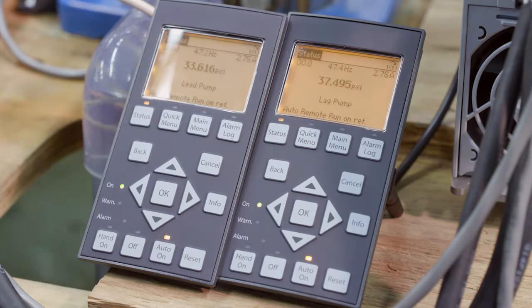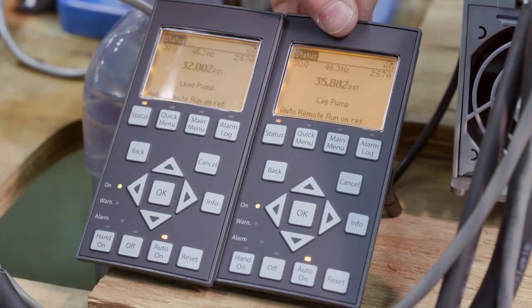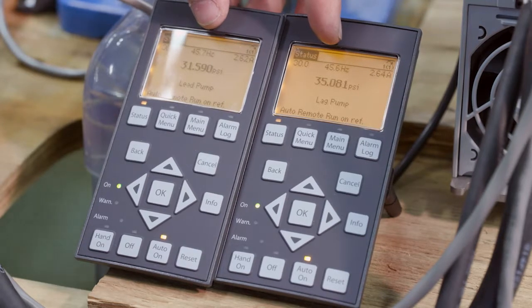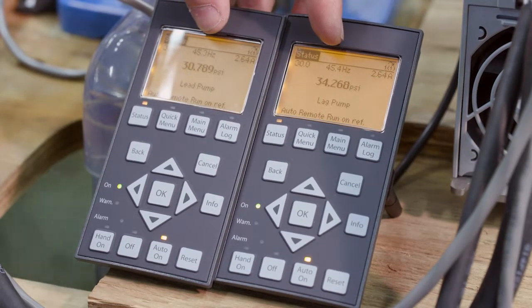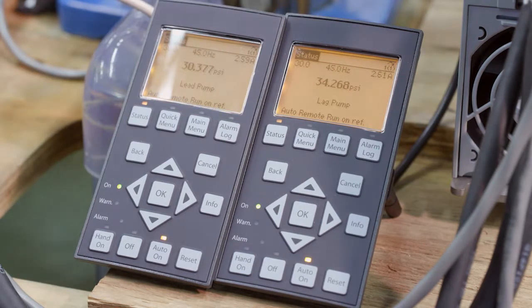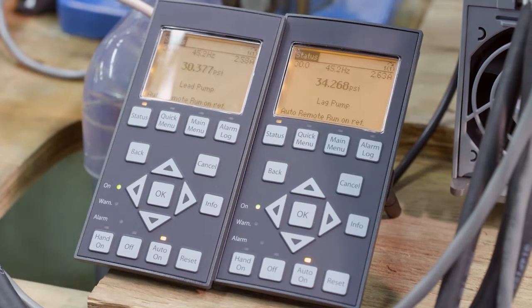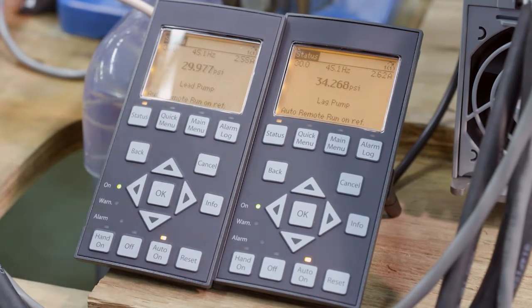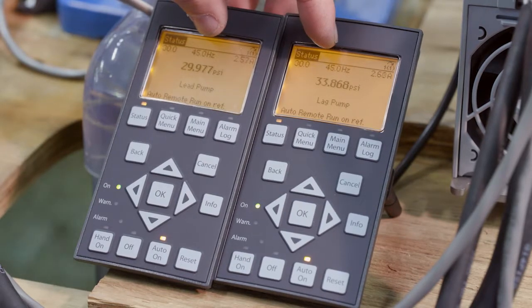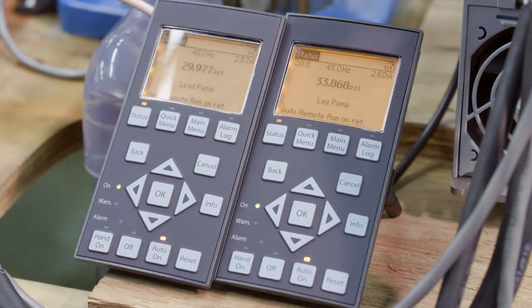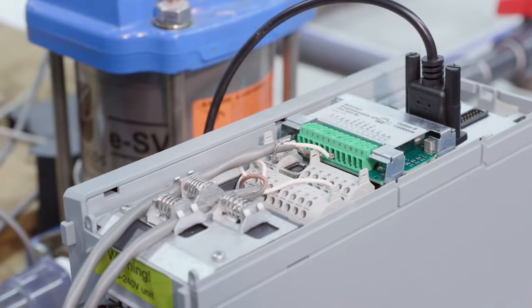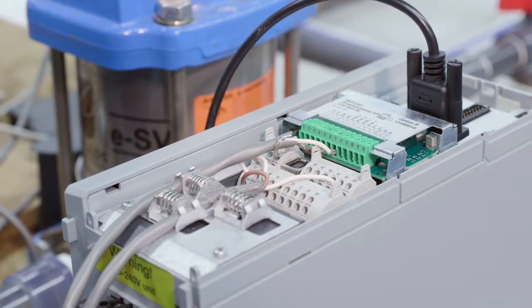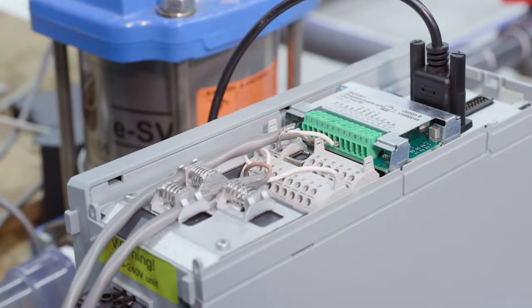So notice the big difference here is when pump 2 came on, they are both operating at the same speed, frequency, and so that is synchronous. So the one addition in terms of your advanced platform is you don't always have to run in synchronous. There are other modes, for example, like the multi-master, multi-control that we just showed you. So we talked about the additional options that you have for multi-pump operation. We showed 2 of them.